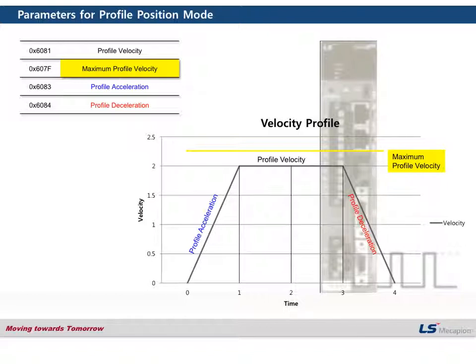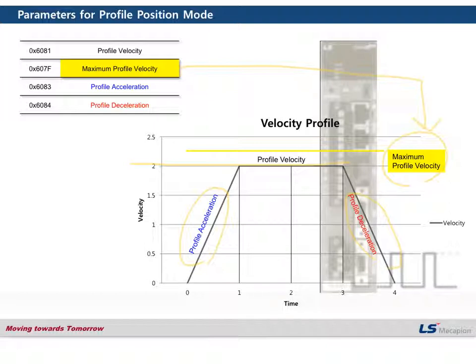This is the example of the profile in PP mode. As we checked on the previous page, there is an acceleration section, a deceleration section, and a constant velocity section. These parameters are set by the user depending on the system and are for profile position mode only. Maximum profile velocity is used to limit the velocity, and profile velocity sets your target velocity. You can also set the profile acceleration and profile deceleration here.